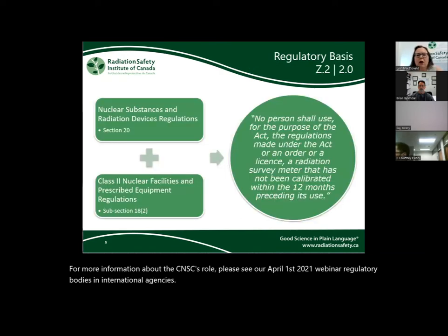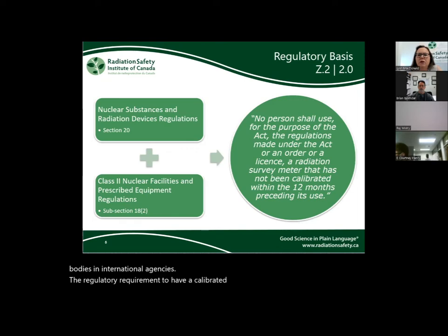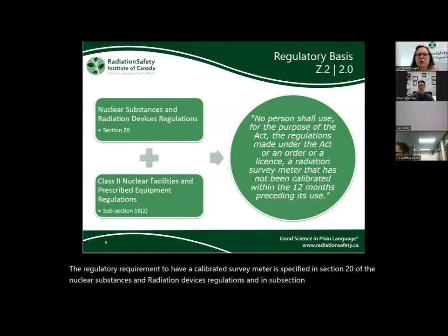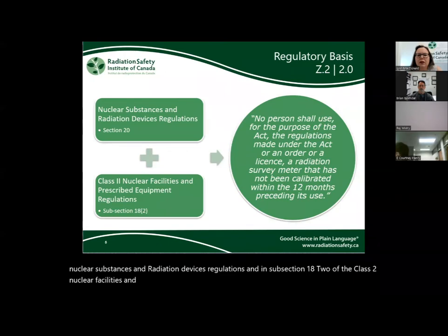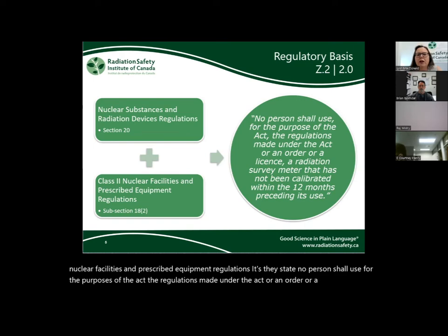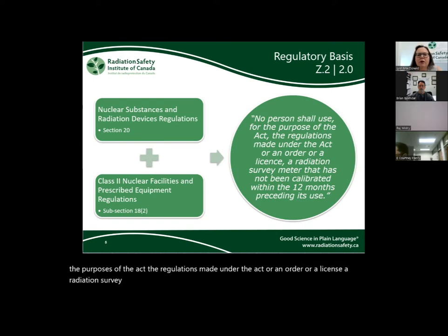The regulatory requirement to have a calibrated survey meter is specified in Section 20 of the Nuclear Substances and Radiation Devices Regulations and in Subsection 18.2 of the Class II Nuclear Facilities and Prescribed Equipment Regulations. They state, no person shall use, for the purposes of the Act, the regulations made under the Act, or an order or a license, a radiation survey meter that has not been calibrated within the 12 months preceding its use. Note that it says 12 months, not 1 year, so it's the date it has to be calibrated before that expiry date of 12 months goes by.